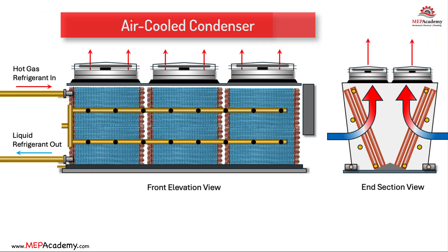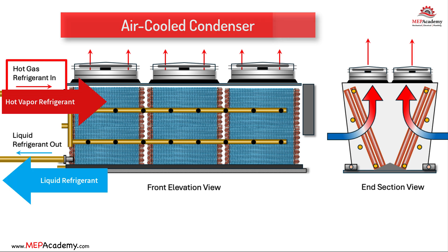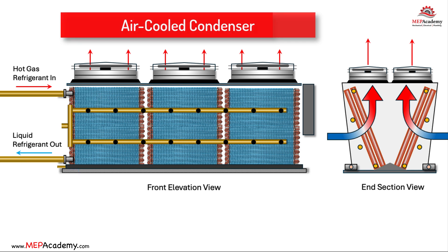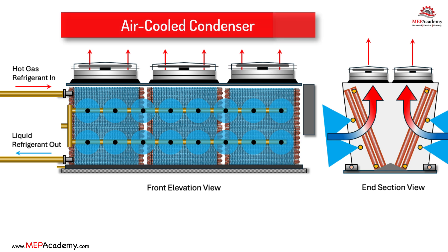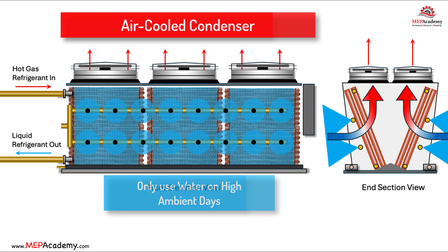For the air-cooled condenser with water spray, the refrigerant vapor enters the condenser and leaves as high-side refrigerant liquid. The system will turn on the water spray when it fails to maintain the refrigerant condensing pressure. The water is sprayed outward away from the coil into the air-stream being pulled across the coil by the fans. The heat from the hot refrigerant is transferred to this cooler air, causing the refrigerant to condense into liquid. The condenser conserves water by running dry and only spraying water when ambient conditions require a lower entering air temperature, making these systems recommended for high ambient dry bulb climates or high temperature applications.